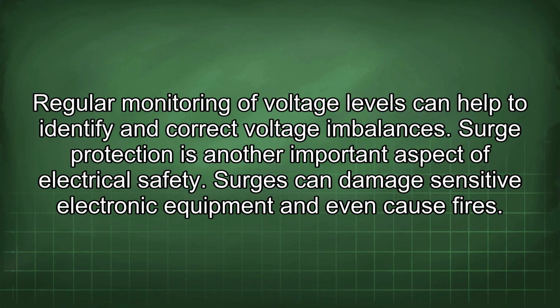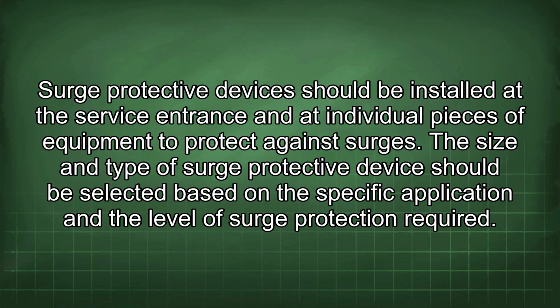Surge protection is another important aspect of electrical safety. Surges can damage sensitive electronic equipment and even cause fires. Surge protective devices should be installed at the service entrance and at individual pieces of equipment to protect against surges.